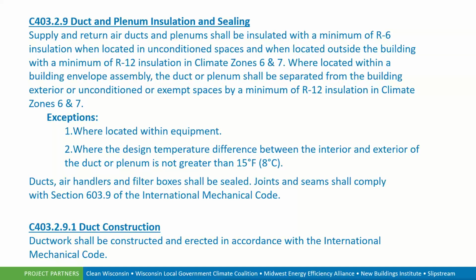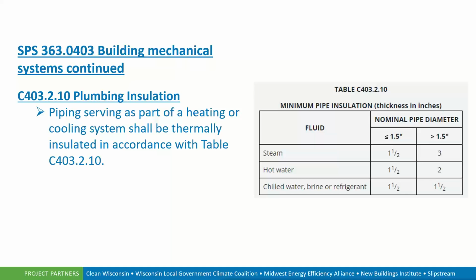And you see that again, there are exceptions where they're located within the equipment itself, or if the design temperature difference between the interior and exterior of the duct or plenum is not greater than 15 degrees. As with the residential code, all ducts, air handlers, and filter boxes need to be sealed, and it needs to fall in line with section 603.9 of the International Mechanical Code. So any seams within the ductwork, connections, all that needs to be properly sealed so that we have air delivery as intended. Ductwork should be constructed and erected in accordance with the IMC, or International Mechanical Code. Piping insulation. There's a requirement specifically for piping insulation, depending upon whether it's steam, hot water, or chilled water. Again, table 403.2.10 gives you that insulation requirement based on the nominal pipe diameter.